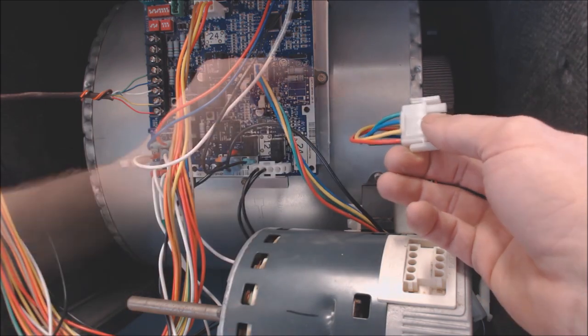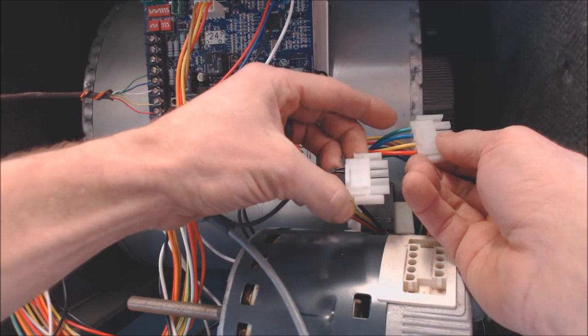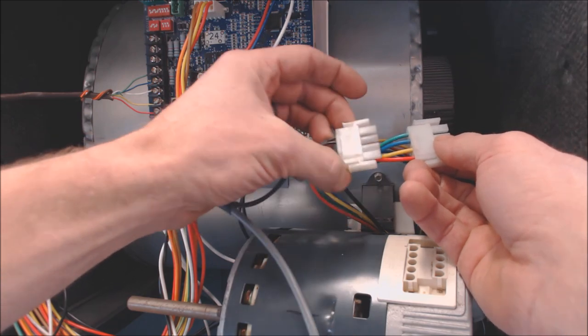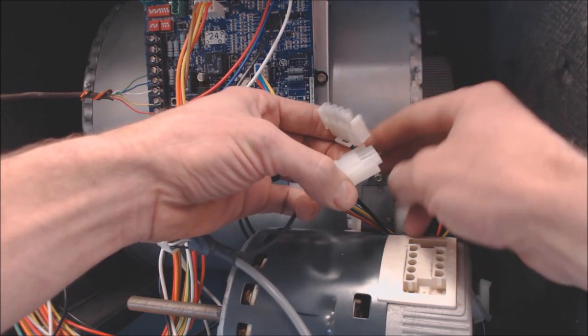...you can actually bypass that by just looking to see which wires need to be powered. So in this case, it's green and blue, and that's going to be the 24 volt signal that we need to send to that blower motor in order to have it turn on.